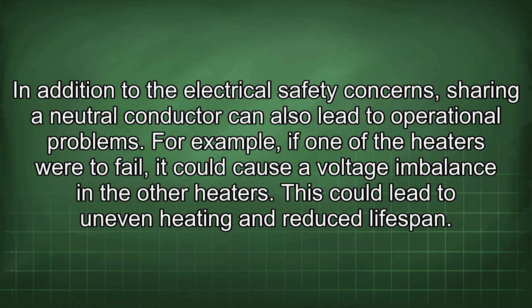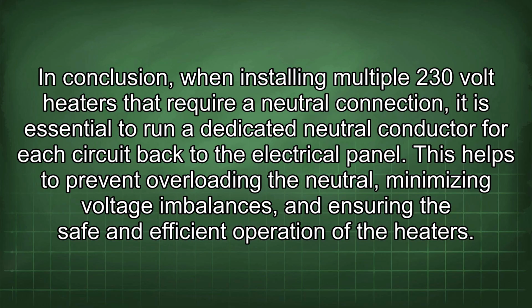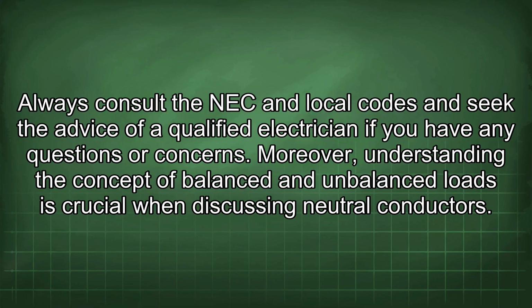In addition to the electrical safety concerns, sharing a neutral conductor can also lead to operational problems. For example, if one of the heaters were to fail, it could cause a voltage imbalance in the other heaters. This could lead to uneven heating and reduced lifespan. In conclusion, when installing multiple 230-volt heaters that require a neutral connection, it is essential to run a dedicated neutral conductor for each circuit back to the electrical panel. This helps to prevent overloading the neutral, minimizing voltage imbalances, and ensuring the safe and efficient operation of the heaters. Always consult the NEC and local codes and seek the advice of a qualified electrician if you have any questions or concerns.